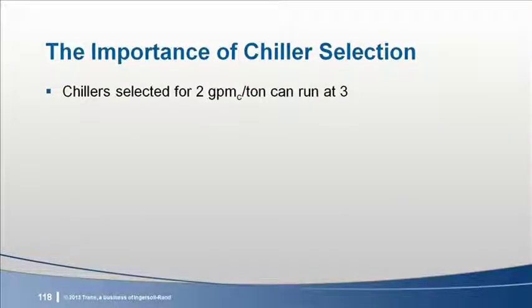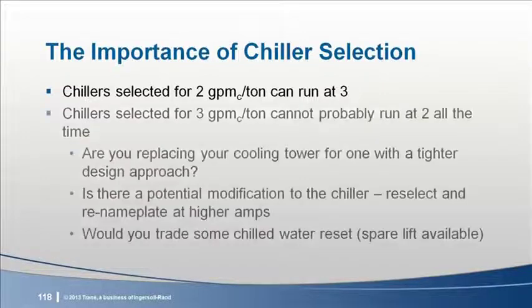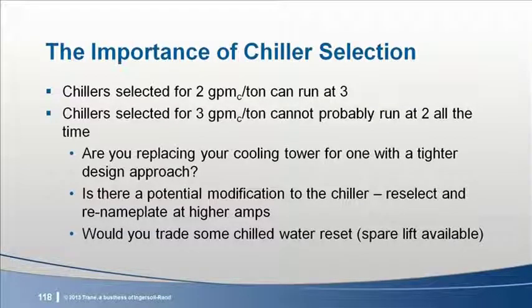You might be looking at a new pump and motor suitable for application with a variable speed drive. Now, generally speaking, centrifugal chillers selected for 2 GPM per ton can run at 3, but chillers selected for 3 GPM per ton probably encounter limits when trying to run at 2, at some combinations of chiller load and wet bulb conditions. What else are you doing at this time? Can you get a tower with a tighter approach temperature? For example, changing from a 7-degree approach to a 5-degree approach? The tower will be larger, but it may help your existing chillers tolerate a reduction in condenser water flow.